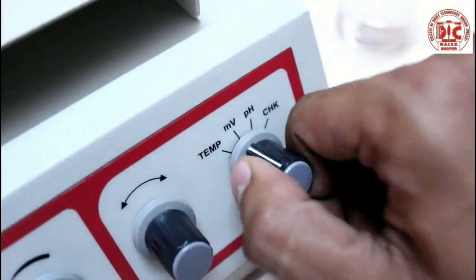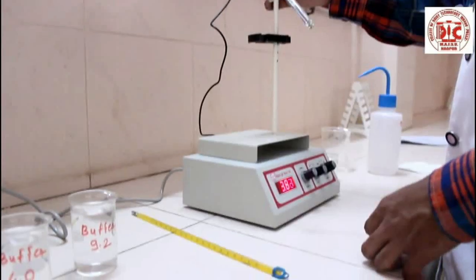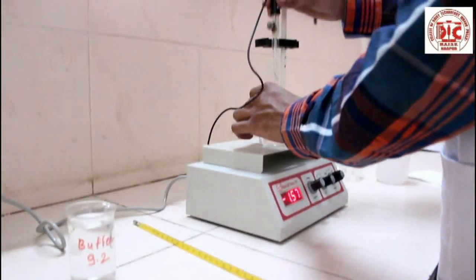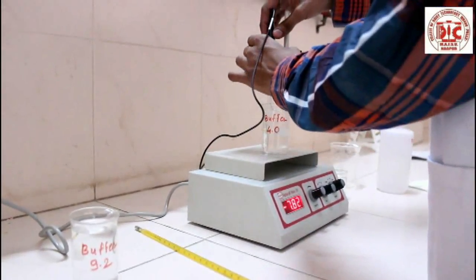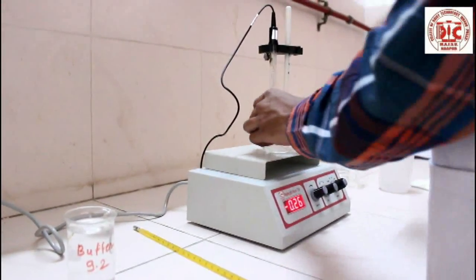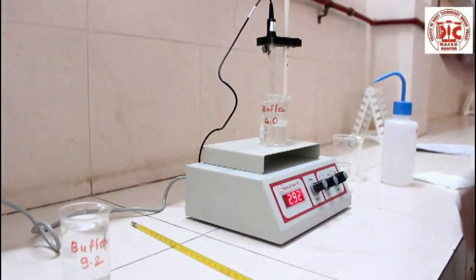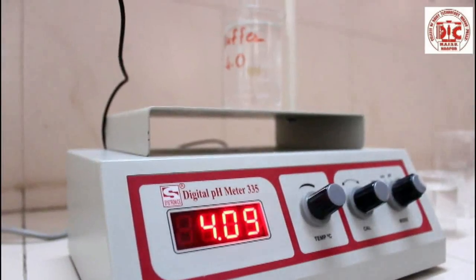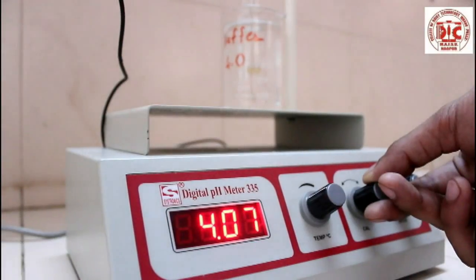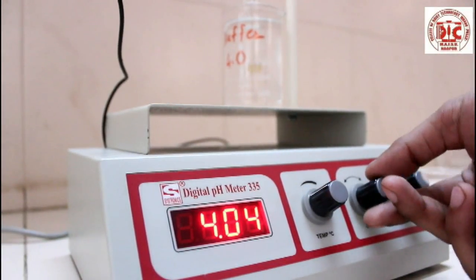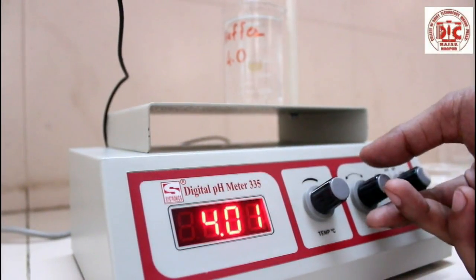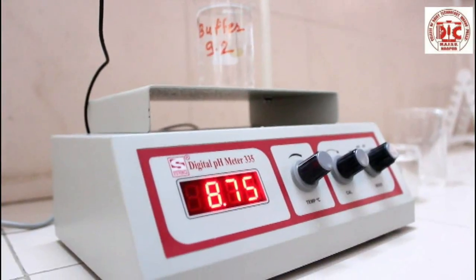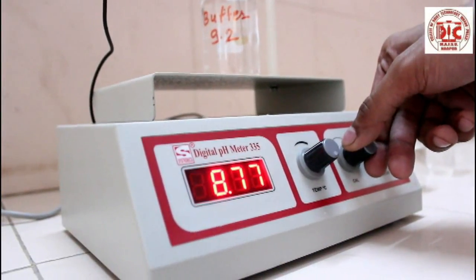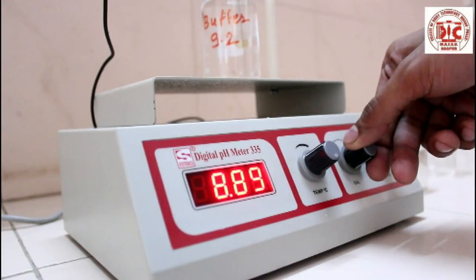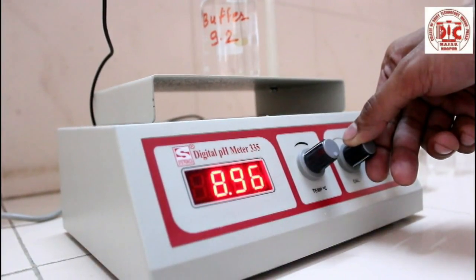Standardize the pH meter electrodes. Immerse the electrodes in a buffer solution having pH 4 taken in a small beaker. Switch on the instrument to the proper range. Adjust the standardization control knob until the meter indicates the exact pH of the buffer. Likewise, standardize the pH meter electrodes against a buffer solution of pH 9.